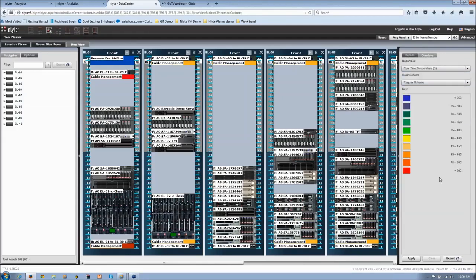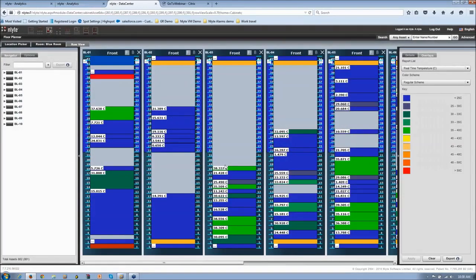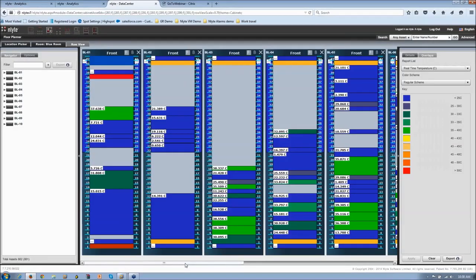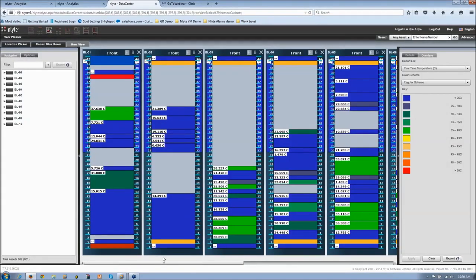Let's look at temperature first. For the temperature inside, we can get the inlet temperature readings of each device, so we can actually get what they're reading and how that's affecting each one of the devices inside a row. So we've turned the whole row, if you like, into sets of readers, giving us that across the data center or across the row view of temperature reading or inlet temperatures.